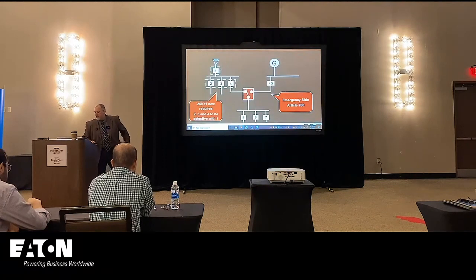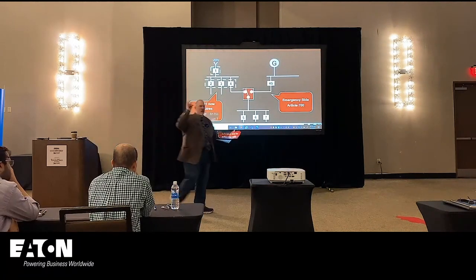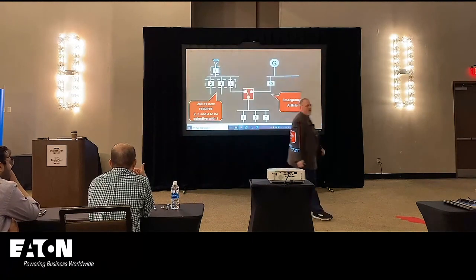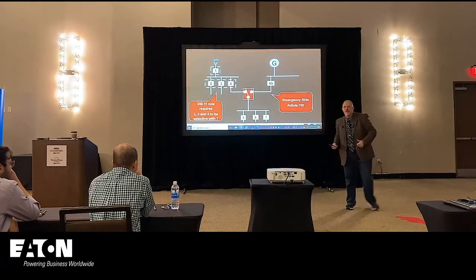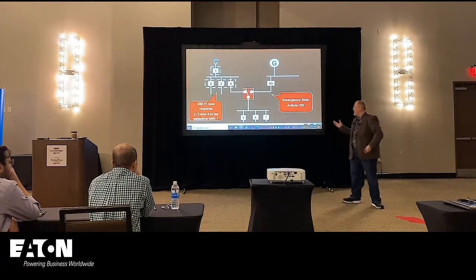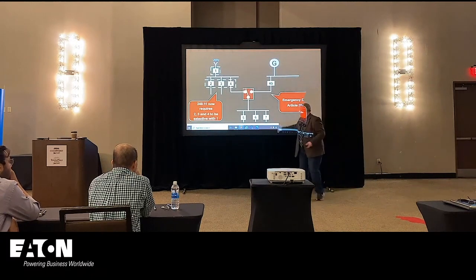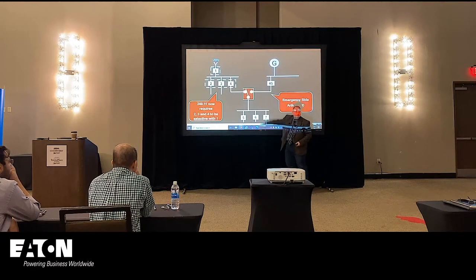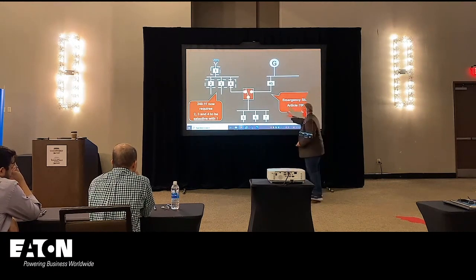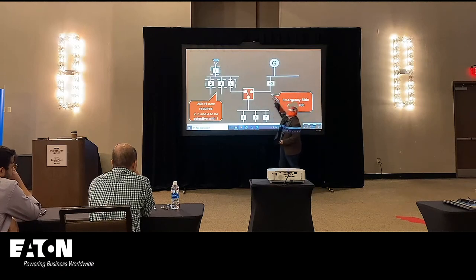So selective coordination, emergency side. So how many people selectively do selective coordination studies? Oh man, I love all of you. Excellent. You know, it's beautiful. So all of this on the right-hand side is, say, your Article 700 system, right? 700, 701, 708, anything that's on the load side of that transfer switch and feeding the transfer switch from that generator, that's the emergency side.